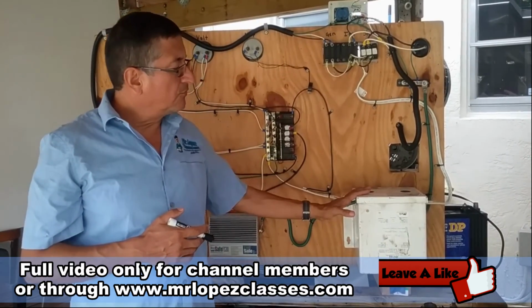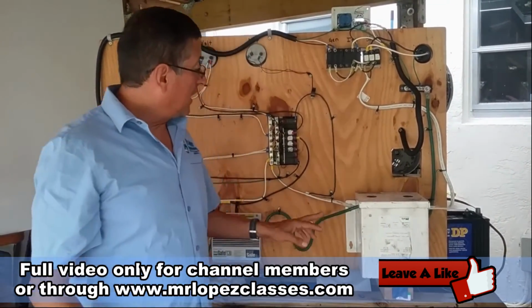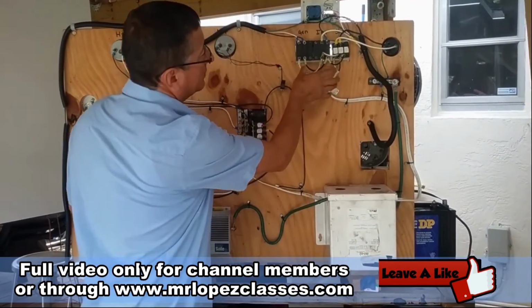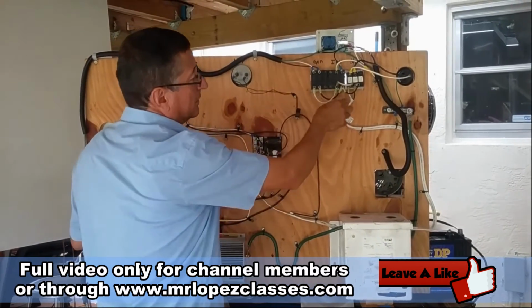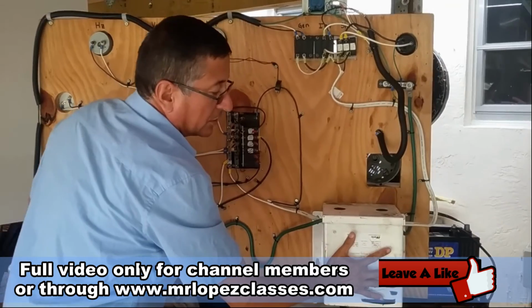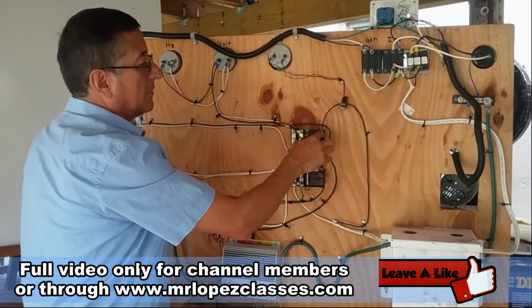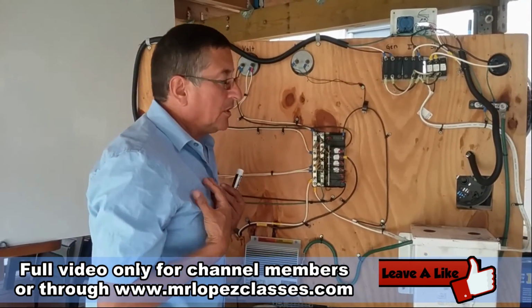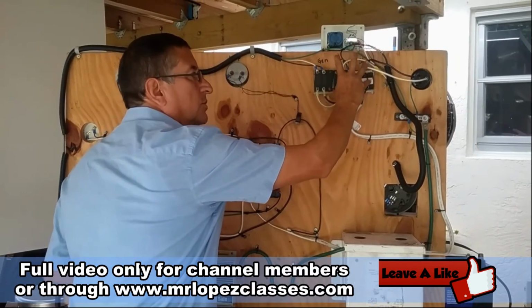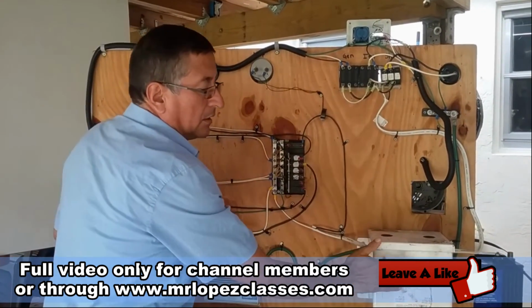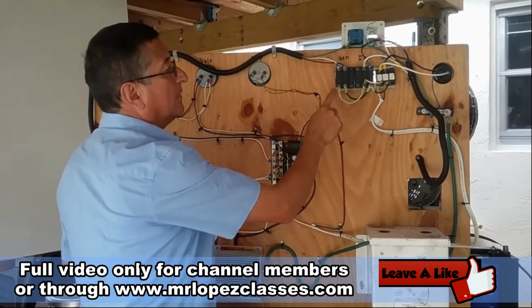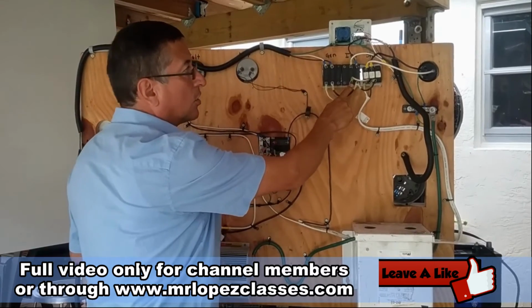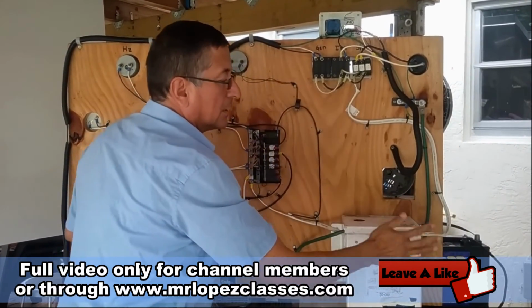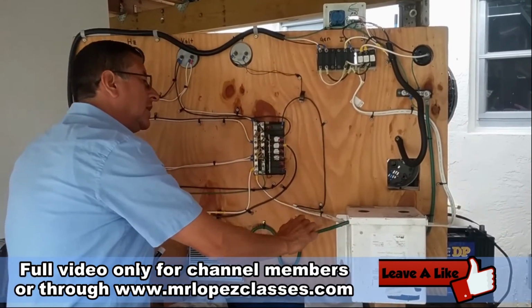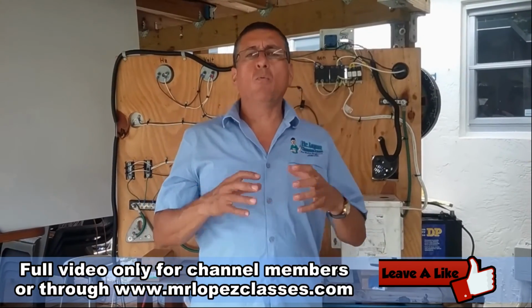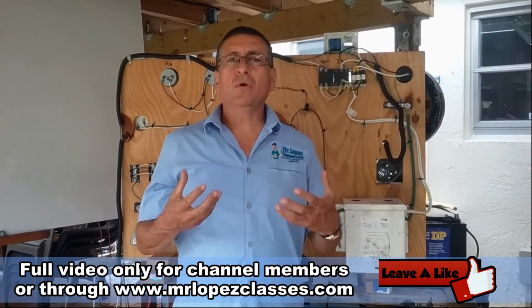Where is the isolated transformer located in a boat? According to my recommendation, it should be located at the output of the switch selector. The power enters the isolated transformer and continues into the main breaker of the AC panel. I recommend placing the isolated transformer between the switch selector and the main panel, because in this location it cleans the signal coming from the generator, the inverter, or shore power. All three of those signals get cleaned, and the output of the isolated transformer will be completely clean.